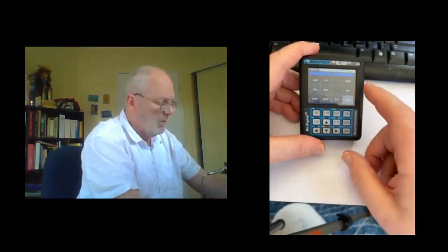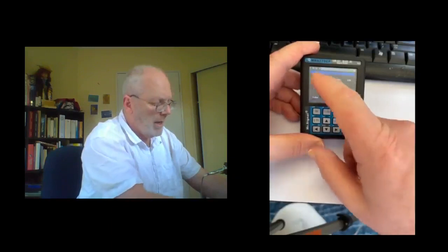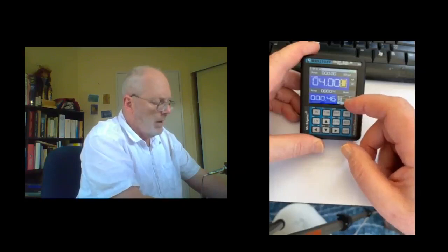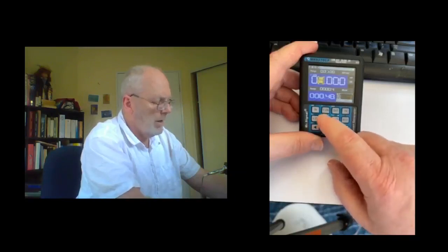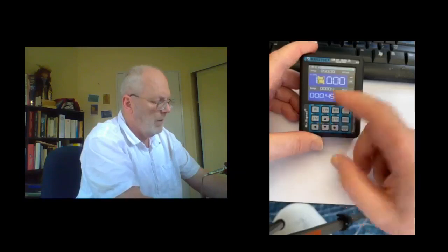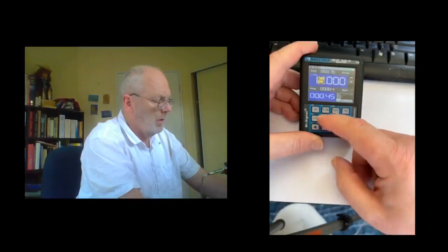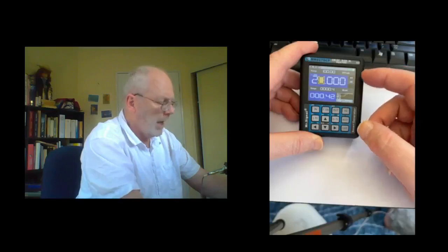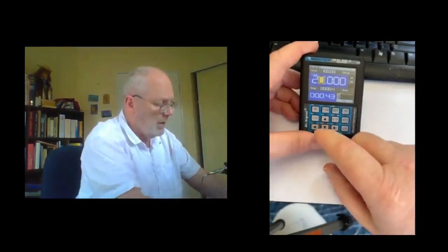Let's take milliamps for example. So I've selected button 1, so just to show you that again, button 1 is milliamps. We know that we're looking at a loop of 4 to 20 milliamps, and we can use the cursor keys to move to where you want to adjust, and we can use the up and down keys to go from 4 to 20, and we can see 12 milliamps representing 50%, all the way up to 20 milliamps and 100%. And we've selected out milliamps. There is a graph as well. I've really not done much with that at this stage.